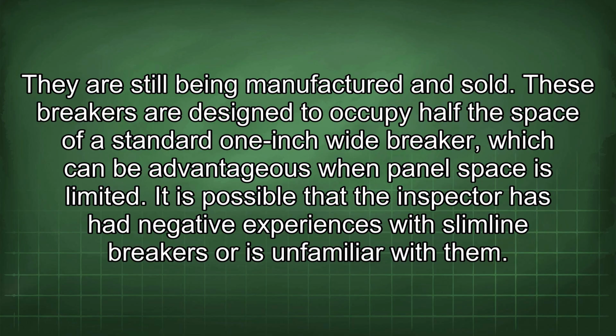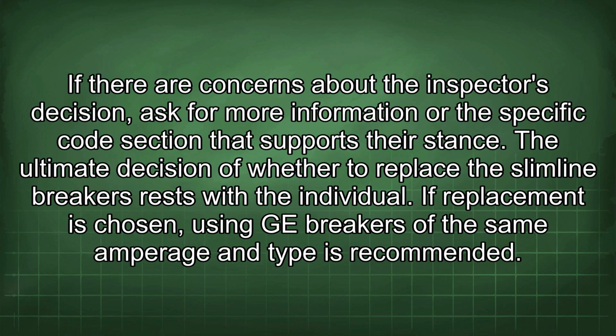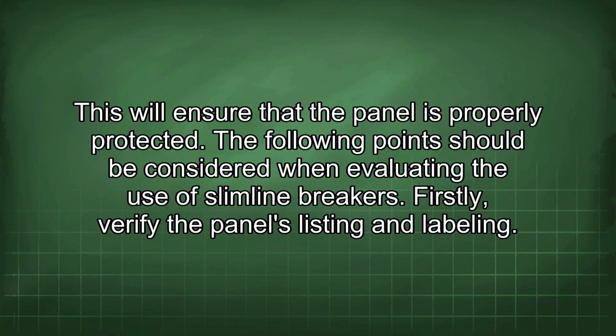These breakers are designed to occupy half the space of a standard 1-inch wide breaker, which can be advantageous when panel space is limited. It is possible that the inspector has had negative experiences with slimline breakers or is unfamiliar with them. If there are concerns about the inspector's decision, ask for more information or the specific code section that supports their stance. The ultimate decision of whether to replace the slimline breakers rests with the individual. If replacement is chosen, using GE breakers of the same amperage and type is recommended. This will ensure that the panel is properly protected.